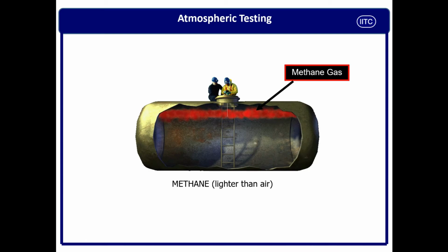Question number 2, where to sample in the storage tank. If the tank is vertical, you have to sample at the top, in the middle, and at the bottom, so that you have gone across, but the spacing should not exceed 4 feet. Why to sample? Because of stratification, when you are going to start your job, whether it is wet or mixed.